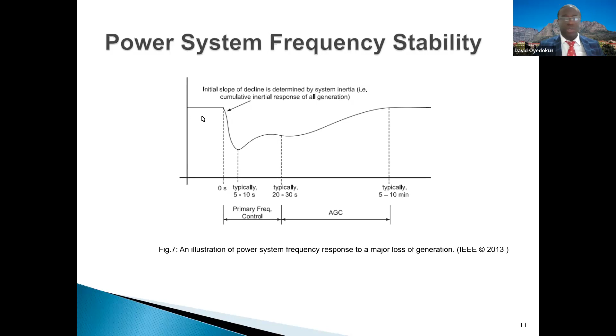So it is more of a challenge to use converter interface generation to provide that reserve. But technically, it's possible to ensure we have that reserve, possibly in battery energy storage, to mitigate it. The second point is that because we have higher variability, we have a higher possibility of frequency excursions out of bound, which places a higher requirement on primary frequency control. So I hope that answers the question.